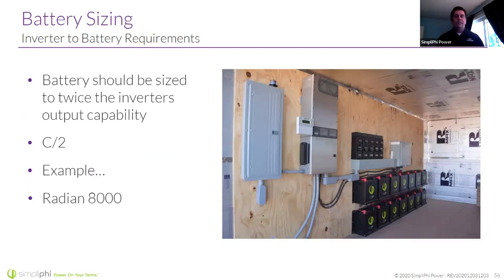When we talk about sizing a system, I talked a little bit about those kilowatt hour values and how that's important for your customer and knowing 80% depth of discharge, what those kilowatt hour values look like. But we also need to understand the kW, the kilowatt value that these batteries can provide. So on the left here, we've got an Outback Radian, looks like an 8048. So that is an 8,000 watt inverter. And if we have 3.8 kilowatt hour batteries, and we can discharge at a C/2 rate, each battery is again giving us about 1.9 kW of power. So 4 of them are not going to provide enough power that Outback could demand.